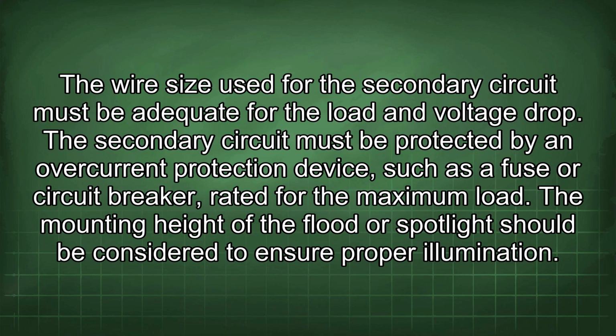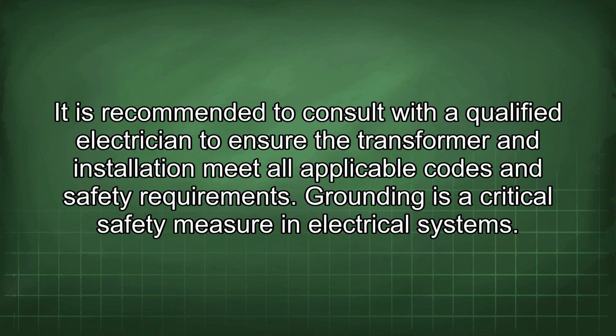The wire size used for the secondary circuit must be adequate for the load and voltage drop. The secondary circuit must be protected by an overcurrent protection device, such as a fuse or circuit breaker, rated for the maximum load. The mounting height of the flood or spotlight should be considered to ensure proper illumination. It is recommended to consult with a qualified electrician to ensure the transformer and installation meet all applicable codes and safety requirements. Grounding is a critical safety measure in electrical systems.